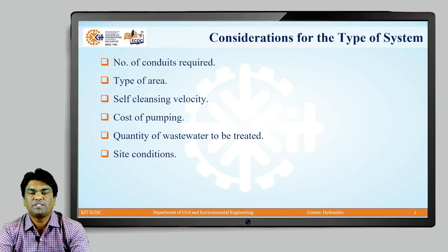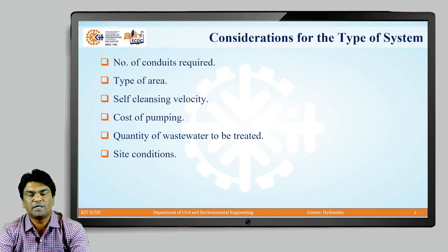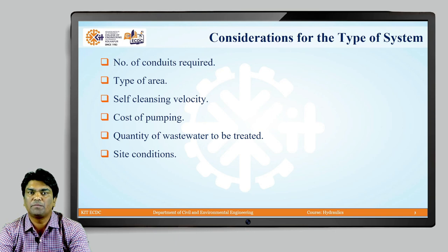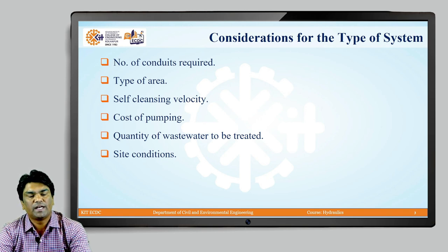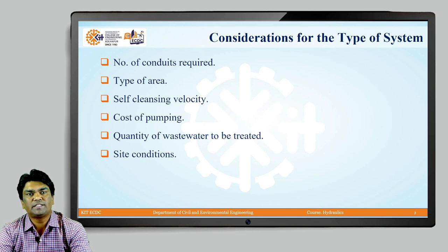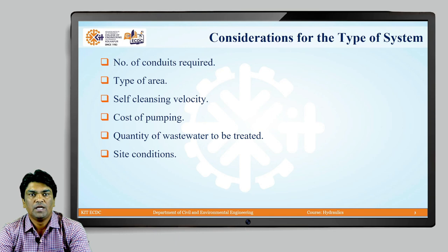First, let us discuss some of the considerations for the selection of type of system. Earlier we studied three types of sewage systems: separate system, combined system, and partially separate system. In the separate system, two types of conduits are required — one to collect sanitary sewage from residential and industrial areas, and the second to collect storm water from roofs and streets. In the combined sewer, a single conduit combines sanitary sewage and storm water. In the partially separate system, sanitary sewage and part of the storm water are collected in a single sewer, with a separate sewer for the rest of the storm water. The number of conduits plays a very important role in deciding the type of system.